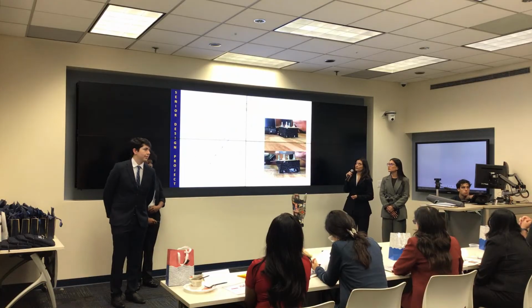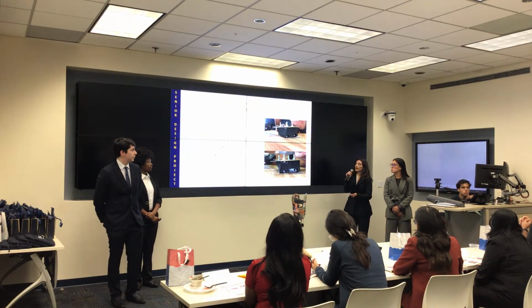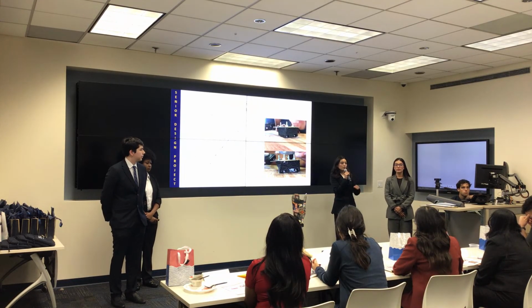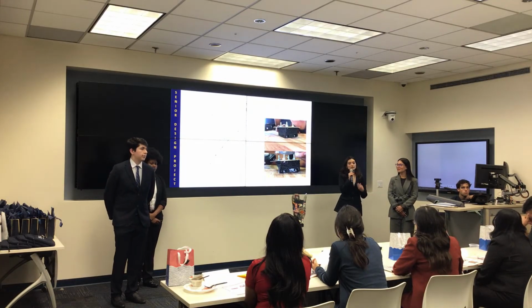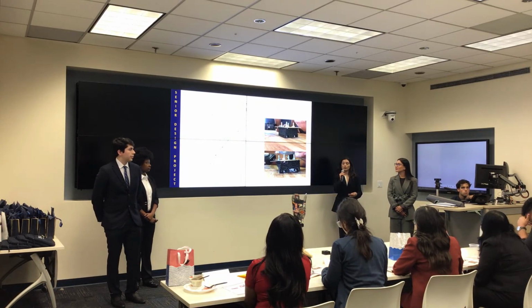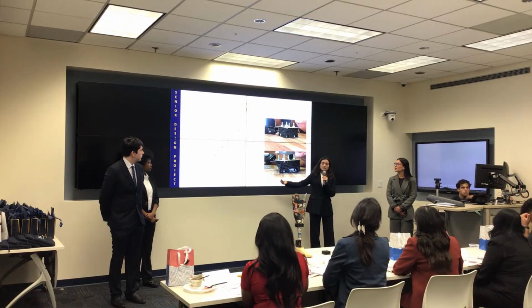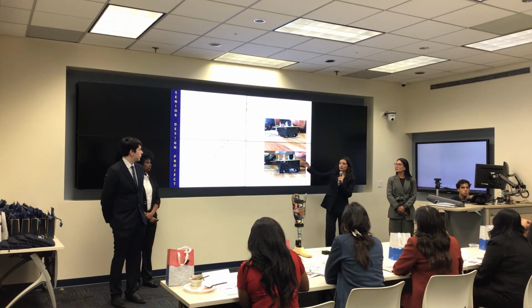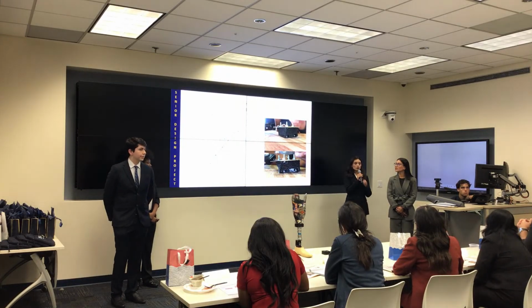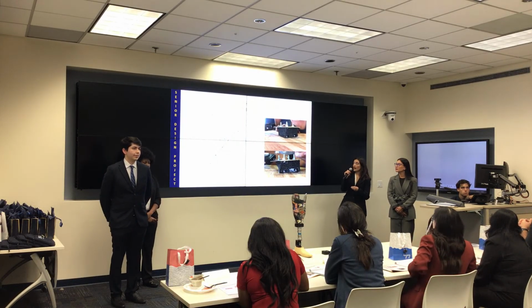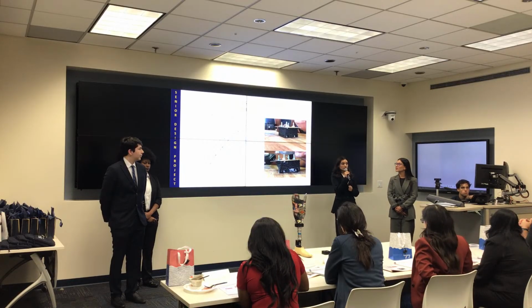Moving on, we also performed a rotational compliance test. We had the module fixed at both ends and had a pulling force applied to the top to see if this 15 degrees of rotation was allowed and more. In this plot, we can see that as the degree of rotation increased, so did the torque, and we can see with the line of best fit, there is a strong relationship for controlled torsional stiffness, indicating we do have that module restoring back to its neutral position.